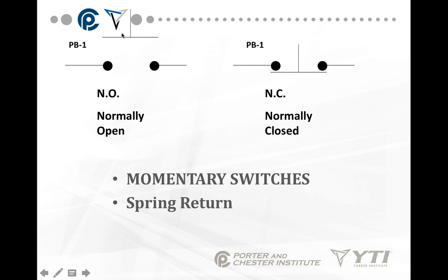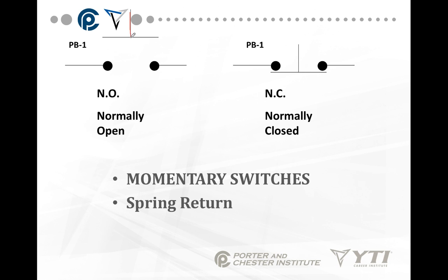Momentary switches are indicated by this T shape. If you look at this switch, we basically have a T — you push it down, it makes contact. You remove the force and it reopens back to its normal position. Here I have a normally closed version — the action would be to push it down, pulling it off the contacts, then release it and it pushes back up. These are considered momentary switches; they do not stay in position.